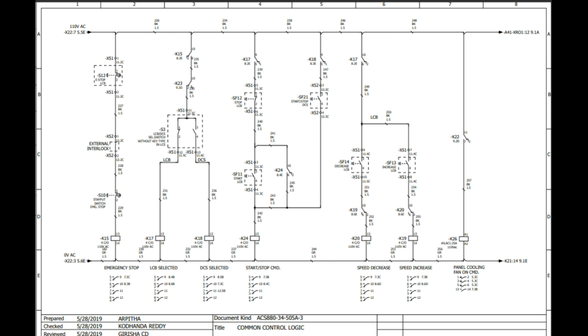Next, if we have to increase and decrease the speed from local mode, then again the selector switch has to be on the left hand side. K17 gets healthy, and on the fifth tapping on the top you can see K17 again. It will feed and go to two different parts, speed decrease and increase. You can see the two dotted boxes that we have to press. For as much speed as we have to increase or decrease, we have to keep the push button pressed. There is no holding contact, but there are interlocks. K19 is the speed increase auxiliary contact, and K20 is for speed decrease. So here you can see both interlocks. Since we cannot give both commands simultaneously, this is very important.